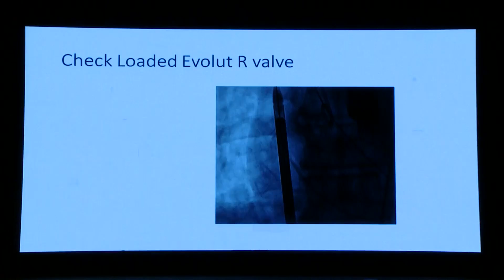Before we do a balloon angioplasty, we always look at the valve, we load the valve properly. It's important to check whether the valve is loaded properly, because very occasionally, when the patient develops severe AR, we need to quickly implant the valve. That is why we have to make sure the valve is well prepared before we do a balloon aortic valvuloplasty. So we have to look at whether there is any misload after loading. It's very important. Check for any large gap between the paddle and the pocket.